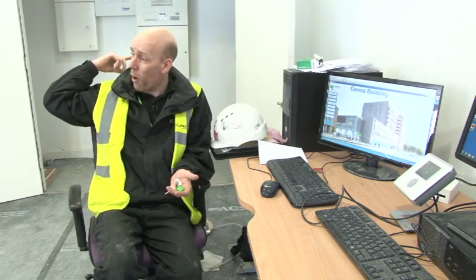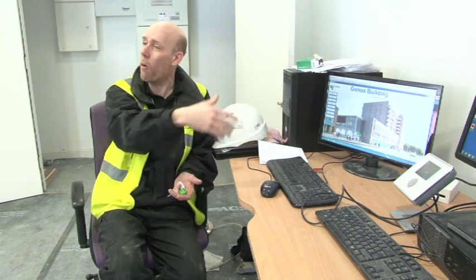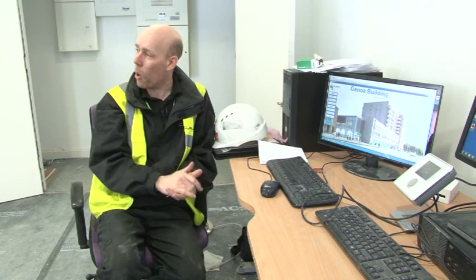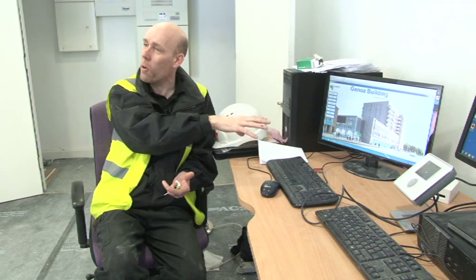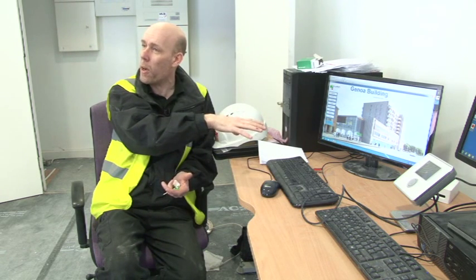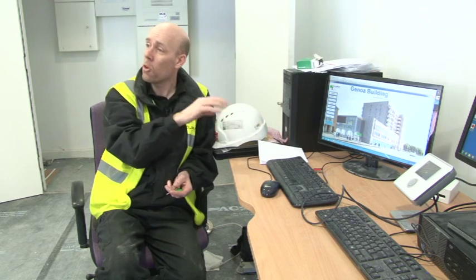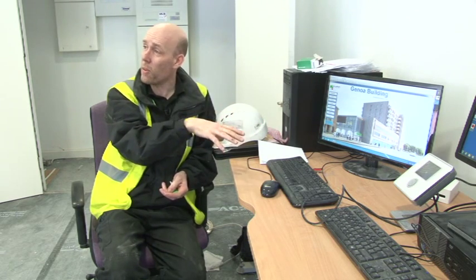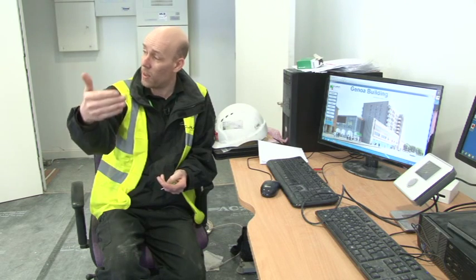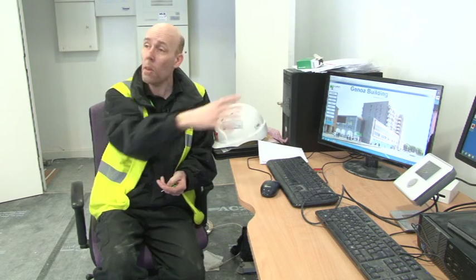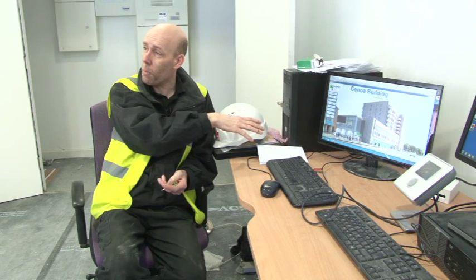Even though you have a fire alarm panel, it will still say the BMS fire alarm has triggered and requires some attendance. If you reset the fire alarm, that alarm will automatically reset. It requires no interference by any maintenance personnel. Some of the alarms on the system are automated, as in if it goes into fault, it will tell you there's a fault. If it clears itself without any intervention, the alarm also disappears from this system.